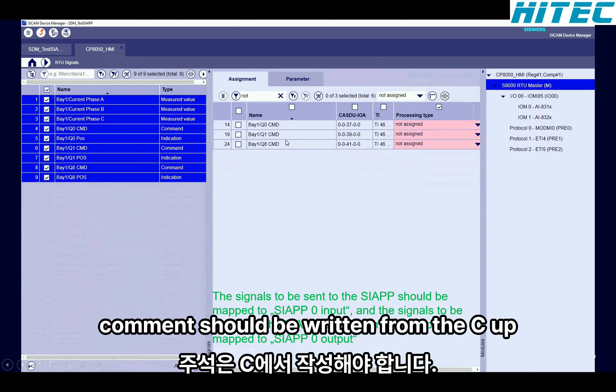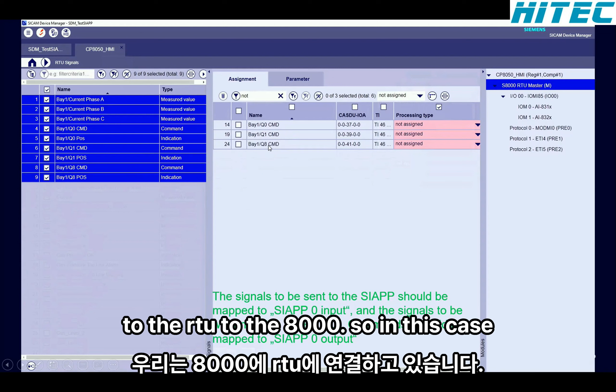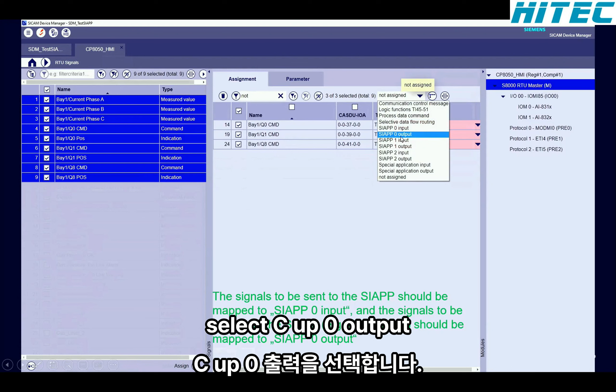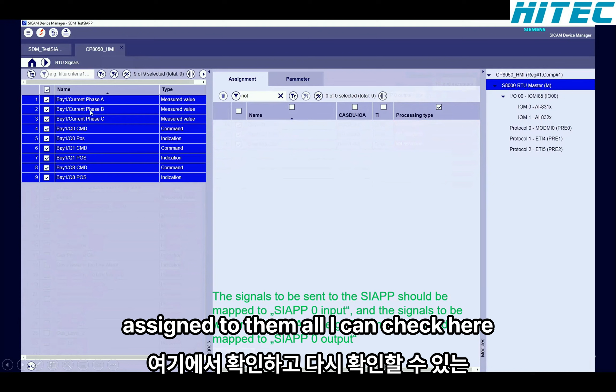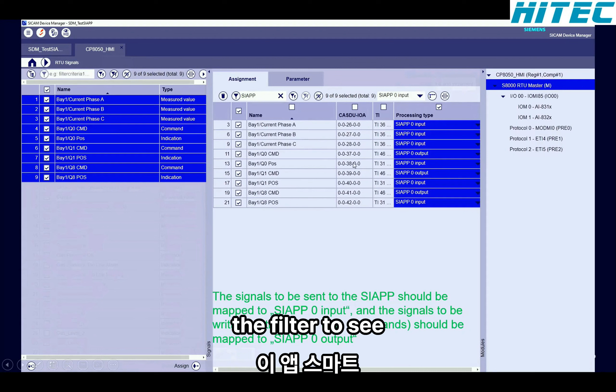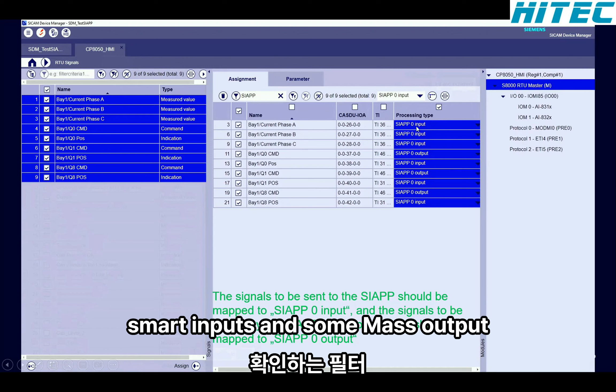And now we have the commands left. The command should be written from the SIAPP, from the web browser we're connecting, to the RTU, to the 8000. So in this case, I mark all of them, and for processing type, I select SIAPP 0 output. Assign to them all. I can check here again the filter to see which signals have been assigned to the SIAPP, some as inputs and some as output.